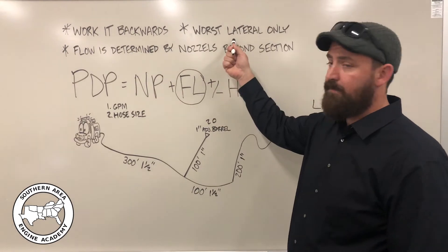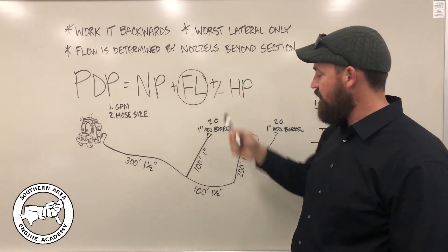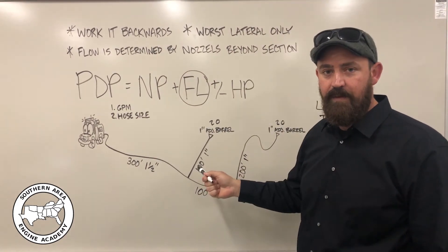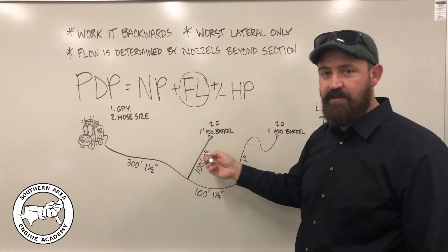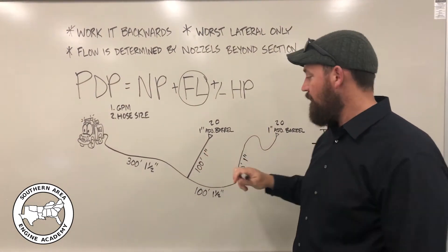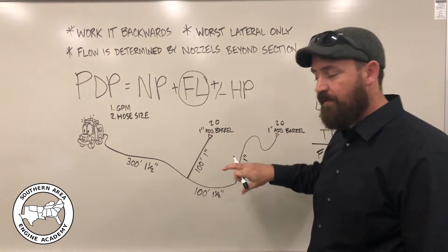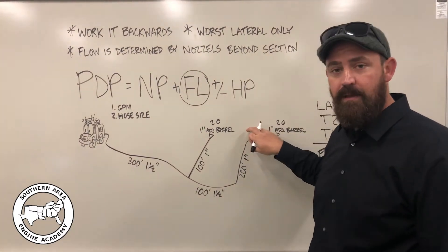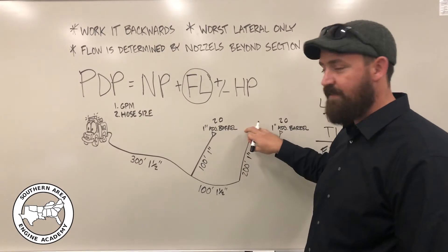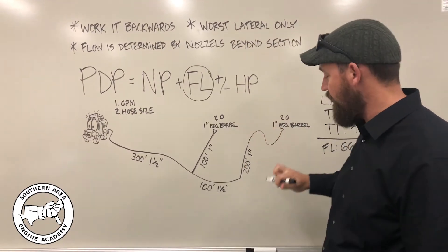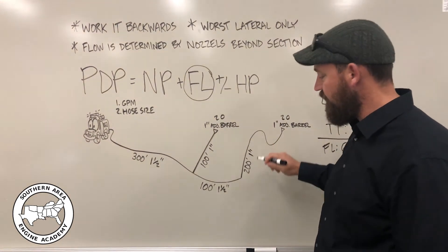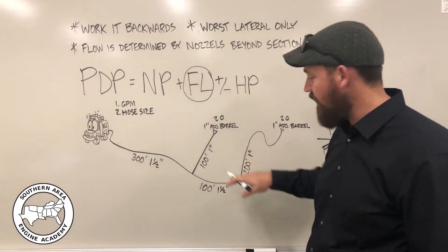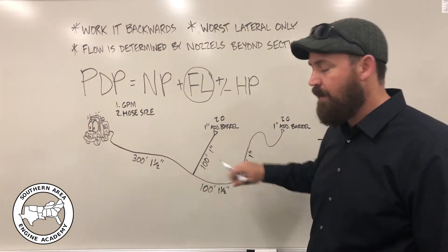Well, that takes us to our next rule of thumb, which is that we're only going to do the friction loss for the worst case lateral. The worst case lateral will be the one that requires the most pressure to operate. In this instance, both of these laterals have the same nozzle on them, which are going to run at the same pressure and they have the same flow. So the longer lateral is going to be the worst case. This one is 200 feet long, so it has more friction loss than the shorter lateral.